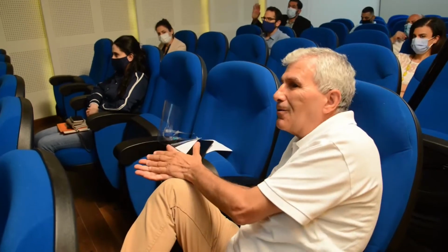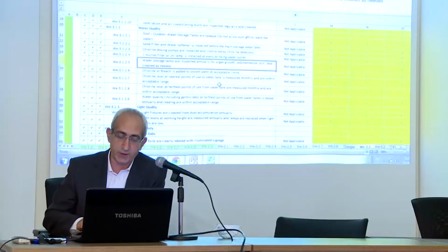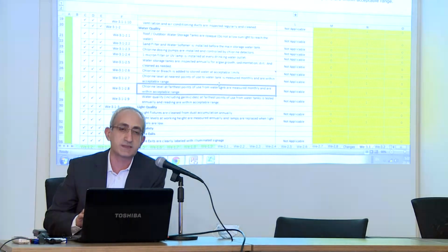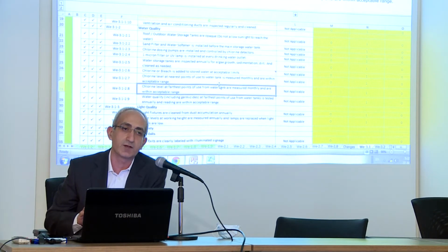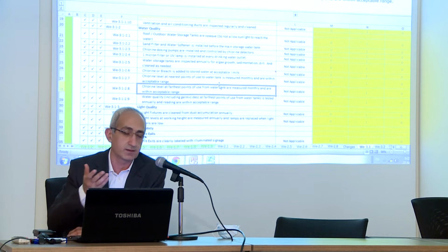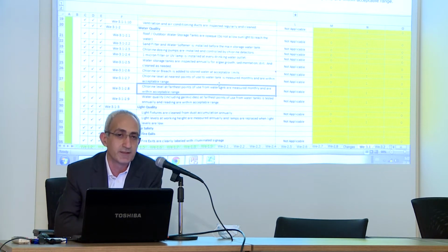With chlorine it will come as a carcinogen. It's widely used, and actually we have items here for testing endpoints and close points to water tanks. I'm open to other suggestions. You need a residual of disinfectant in the water. UV will not give you a residual disinfectant. Usually, you need chlorine or any disinfectant that keeps a residual in the water. UV is at the end point of use. Potable water, so your tank is stainless steel and the network is completely new. You don't need a residual.